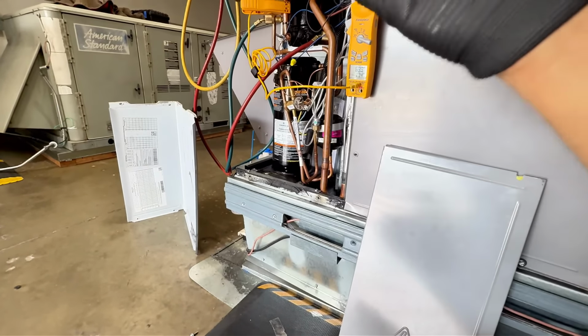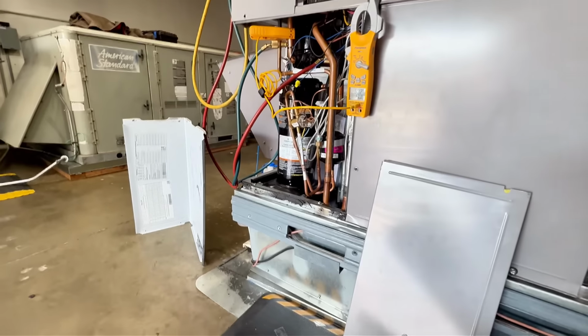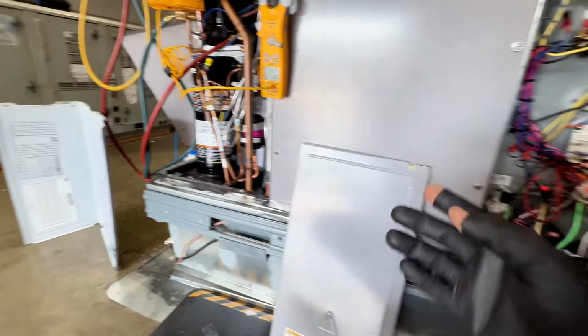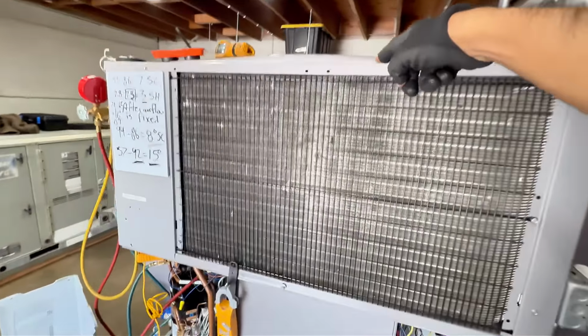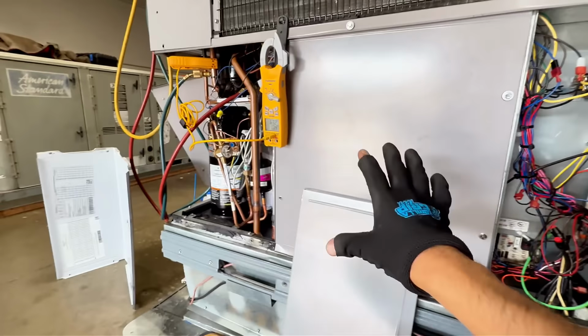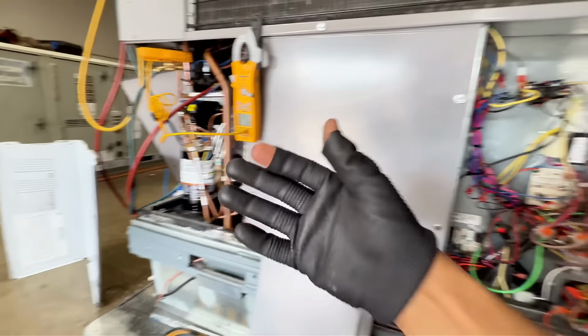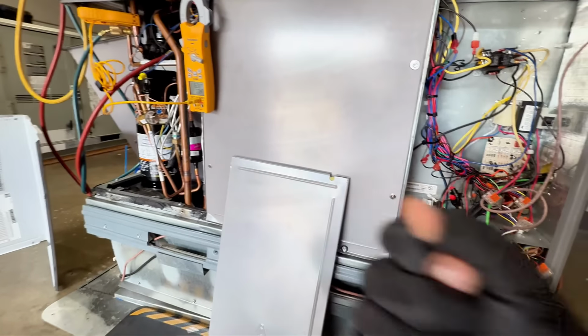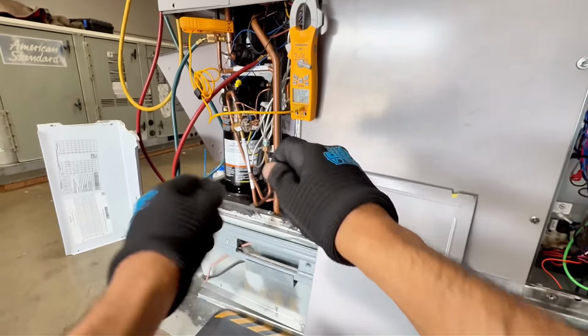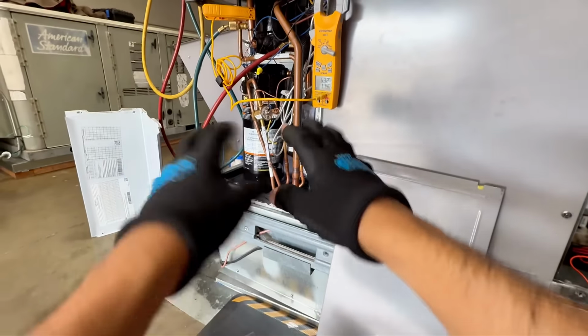You would have to check the refrigerant level, check your capacitor. You've got your indoor motor and your outdoor fan motor, your condenser. You can ohm it out, right? But I'm only going to start ohming out these components that take high voltage if it tripped the breaker or a fuse went bad. I'm not going to right away start, let me ohm it out. It's the compressor, I can make an easy $2,000.